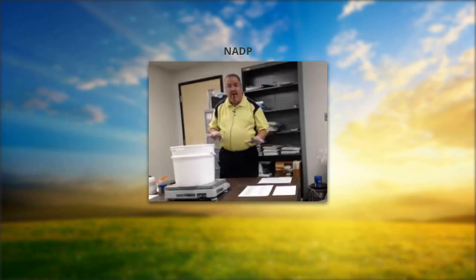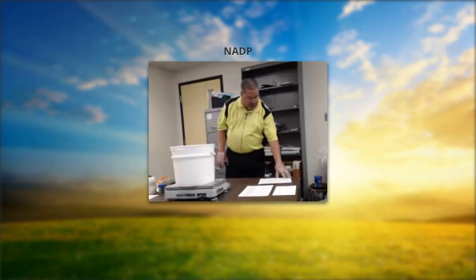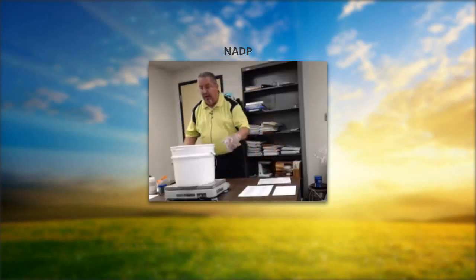I've got a good volume weight. I'm going to transcribe that onto my field form in Section 6, where it says bucket, lid, and sample. Then I'll subtract the bucket weight and the lid weight from my total weight, and that will give me my sample weight.